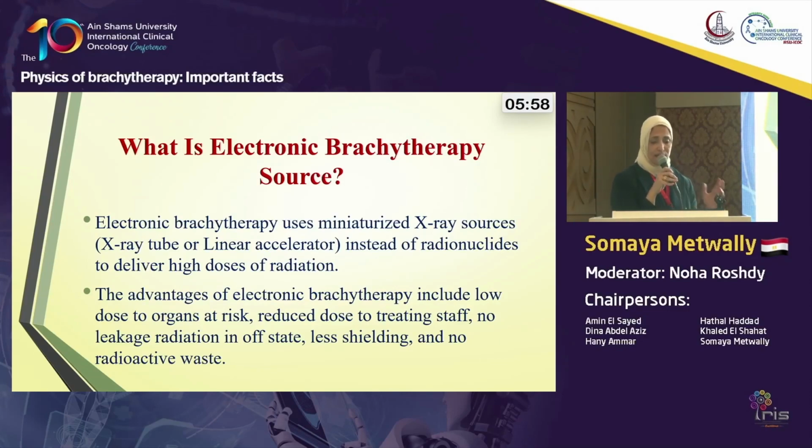The advantages of electronic brachytherapy include low dose, of course, to organs at risk, and it's very important. This is the main advantage, and it also reduces dose to the staff. No leakage radiation in the off state, and also less shielding. I don't need to make shielding for the room. No radioactive waste. I don't have any waste because I don't have any radioactive isotopes, and don't need to transport this radioactive isotope from place to the treatment machine.